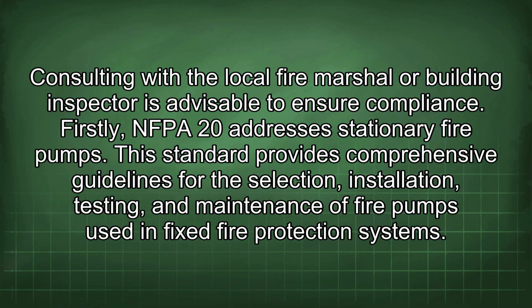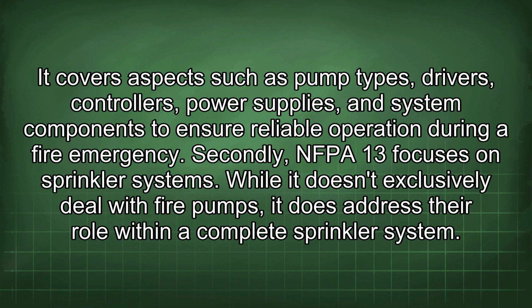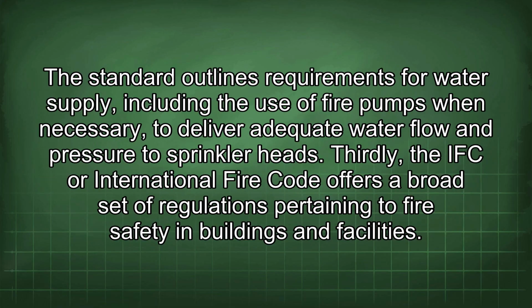Firstly, NFPA 20 addresses stationary fire pumps. This standard provides comprehensive guidelines for the selection, installation, testing, and maintenance of fire pumps used in fixed fire protection systems. It covers aspects such as pump types, drivers, controllers, power supplies, and system components to ensure reliable operation during a fire emergency. Secondly, NFPA 13 focuses on sprinkler systems. While it doesn't exclusively deal with fire pumps, it does address their role within a complete sprinkler system. The standard outlines requirements for water supply, including the use of fire pumps when necessary to deliver adequate water flow and pressure to sprinkler heads.